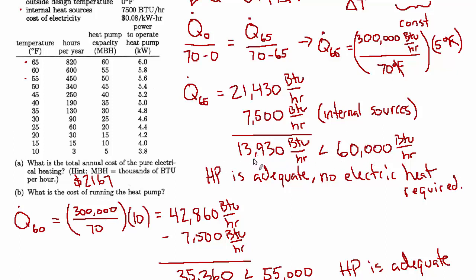It's the ratio of the demand as compared with the capacity, because if this thing only has one speed, right, you turn it on, the compressor stage is on, it's going to start pumping out 60,000 BTUs per hour. That's all it can do. As far as we know, it doesn't say that it has a variable speed compressor or that it has any stages really. So we only really want less than a quarter of this thing's capacity. So it's going to run less than 15 minutes out of every hour is one way to think about it. It'll satisfy the space and it'll turn off, and then it won't need to run for 45 minutes, and then 45 minutes later it'll kick on again, and that cycle will repeat as long as these outside conditions hold.